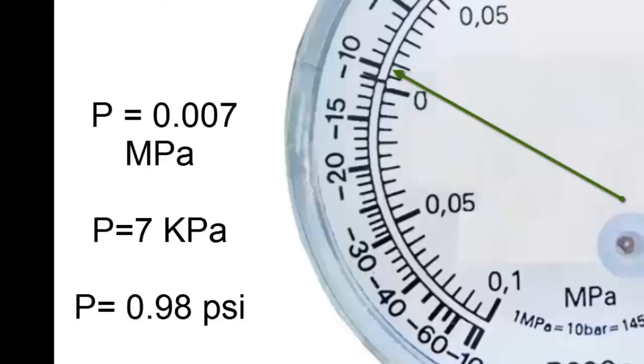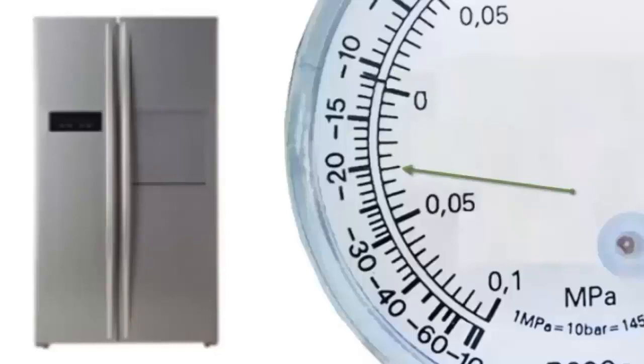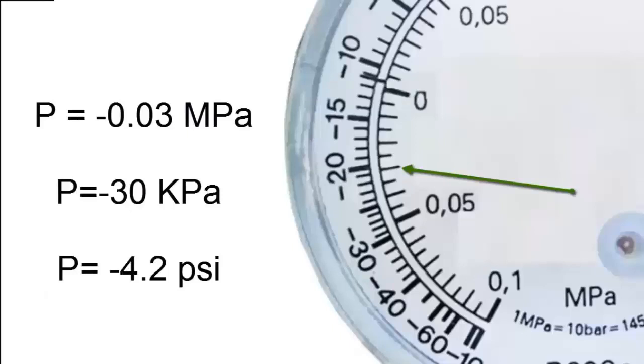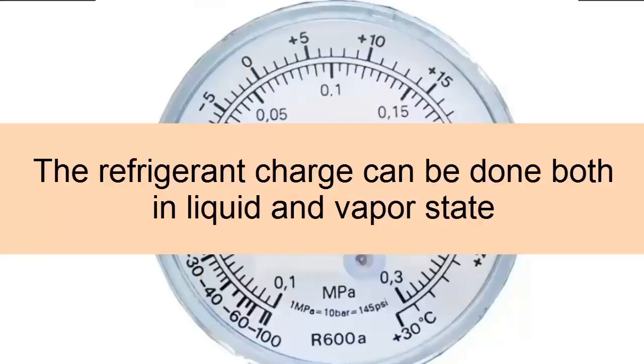In this way the following pressure value is obtained. In addition to using the appropriate pressure gauge, the R600a refrigerant gas charge must be carried out by weight, thus reducing the chances of error. R600a can be charged in both the liquid and vapor phases.